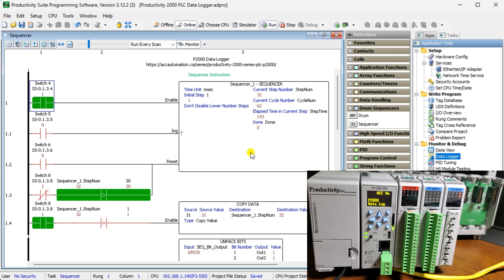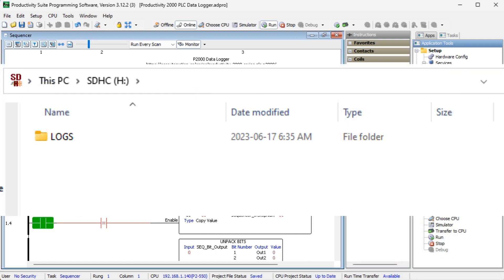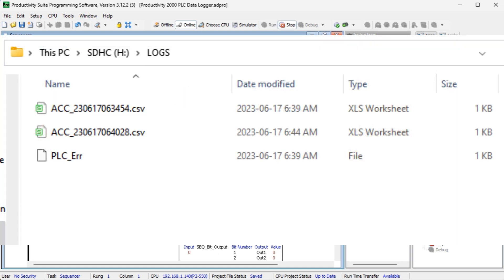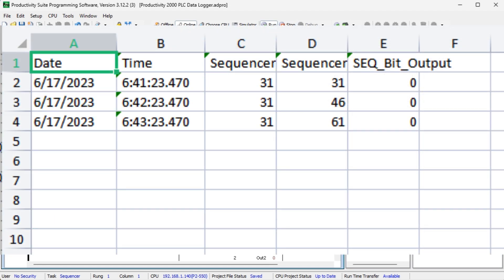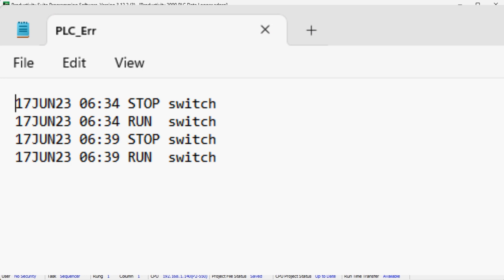Here is the program that we created for the sequencer. You can note that all of the logging is done without a lot of programming. After running the program, we can turn the PLC to stop mode and remove the micro SD card from the CPU unit. Looking at the files on the card, we can see the logs folder. The logged information error and event files will be in the logs folder. We see the three individual tags with the date and timestamp by opening the log file using a spreadsheet program like Excel. Each record is separated by one minute as we specified earlier. The error and event file will show when the new program was put into the CPU, and the run and stop events.